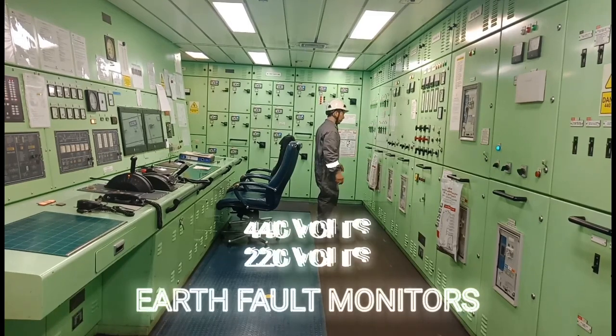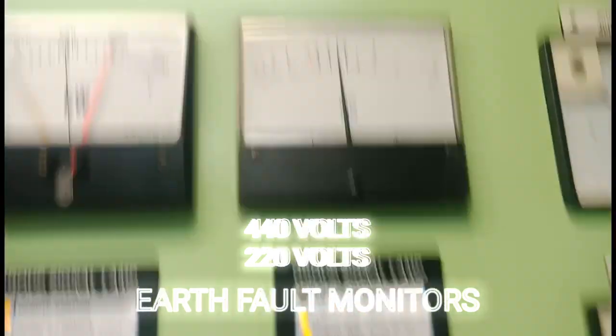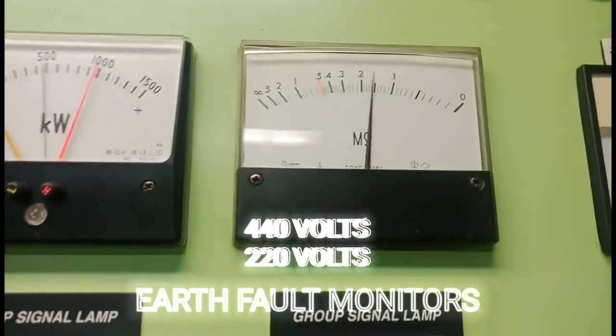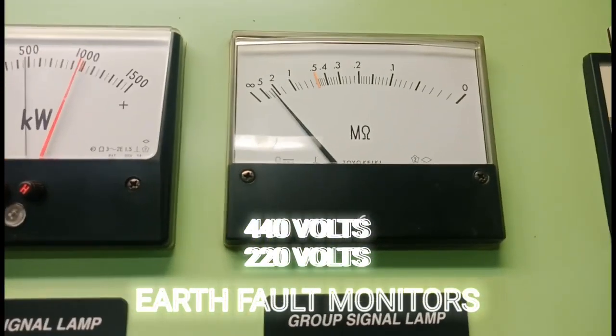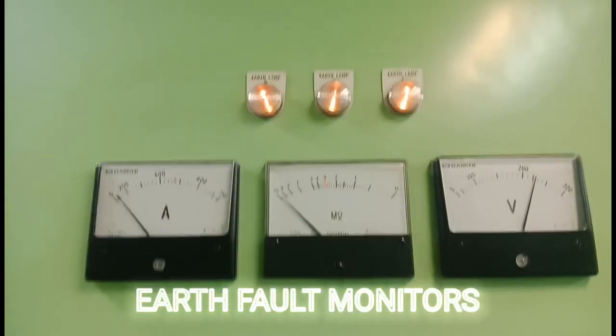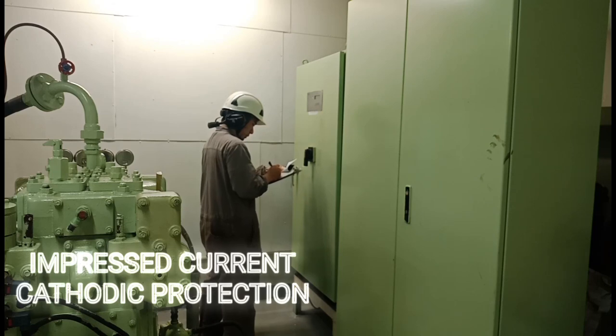It is a daily routine of an ETO to check and test the ship's 440 and 220 volt earth fault monitors to determine if there's any line fault in the entire ship with respect to ground. We also need to record the daily logs.